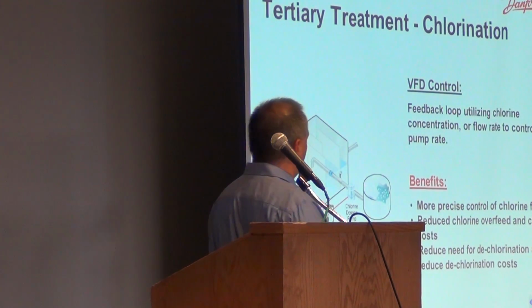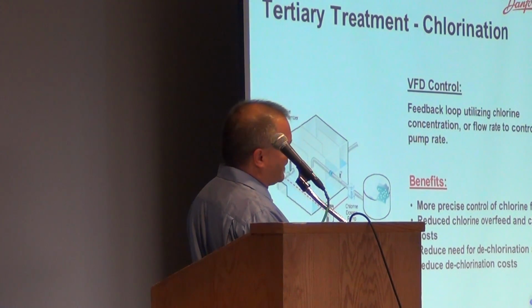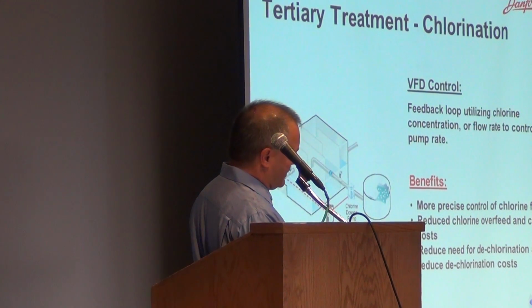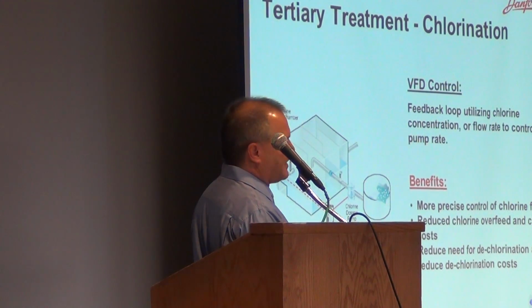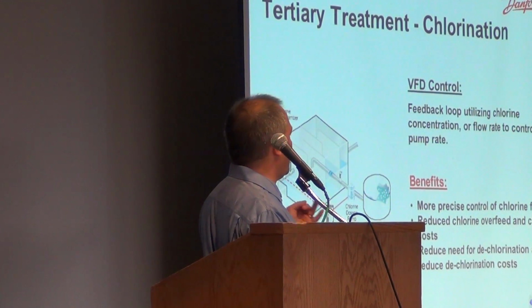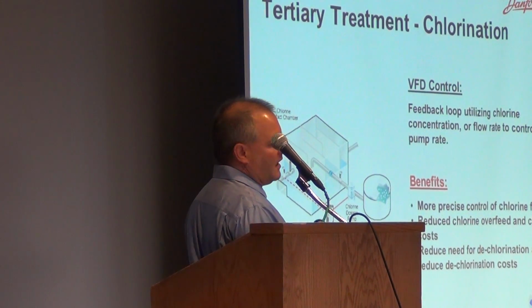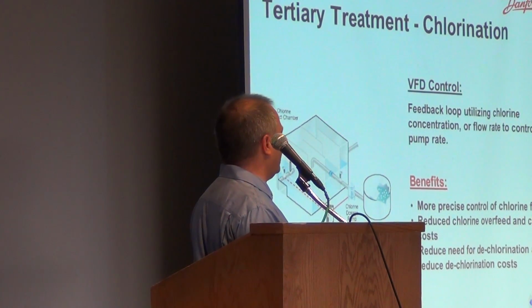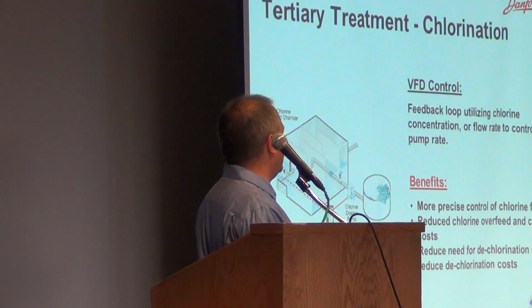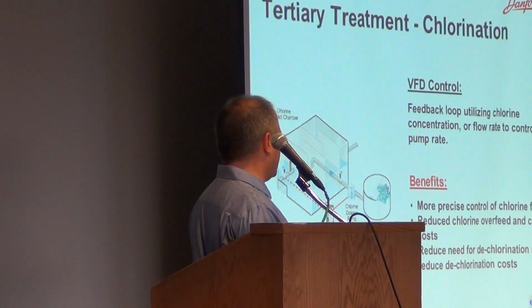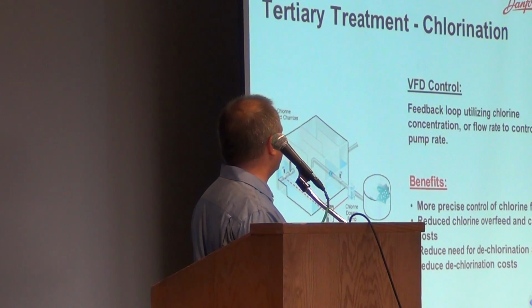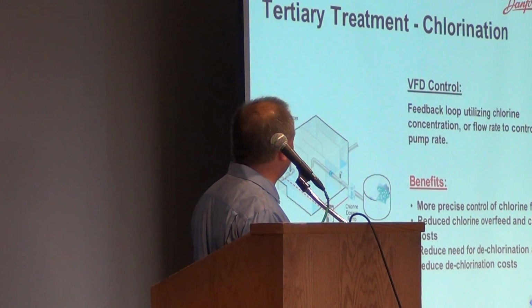In this picture here, they're talking about the drive and how it can control the chlorine dosage. Well, that's what I was saying, where the drive can give us the signal back to a chemical pump to tell it, all right, I'm running at half speed, I'm running at 3/4 speed. I don't need a full dose of chlorine. I only need X amount. Saves on your chemicals, saves on the pump, saves on the system. Here again, talking about the chemicals.